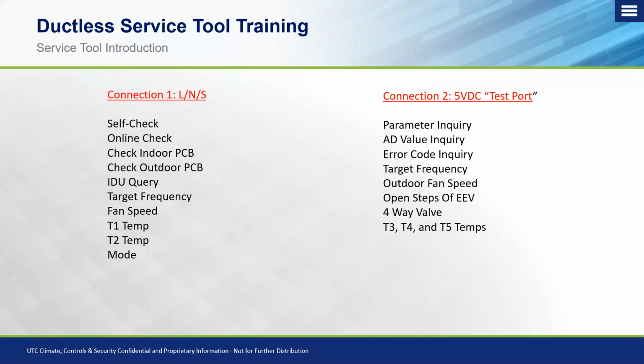If you're trying to test a control board, whether it's an outdoor unit control board, indoor unit control board, or indoor unit fan speed, you would want to use your L, N, and S. So again, this should be definitely something that you look at and decide: am I going to use my high power connection, or am I going to use my low voltage DC to individually test components from the outdoor board?